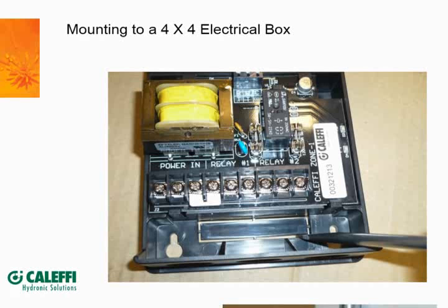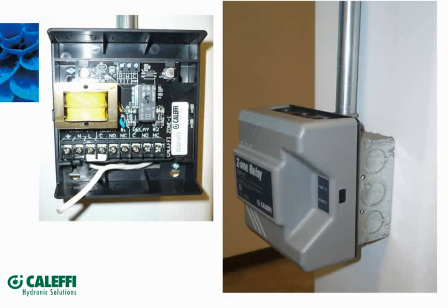But I really like this function here because there are a couple ways you could do this. What's nice about this, if you want to land a conduit or some flex or some liquid tight into a metal box instead of the bottom of the relay box itself, you can land all this stuff and then come back later after the sheetrocking and the painting and everything's done and then put your control on it that way. Or the other thing you could do, if it's new construction, you can buy those metal 4x4 boxes with a nailing plate built right into them. It's welded right onto the side or crimped on the side of it.